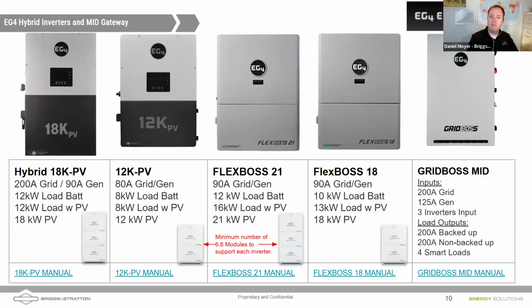So you can see with the 12K PV or the FlexBoss 18, that can only do 10,000 or 8,000 watts from battery to load. So that's the minimum number of batteries you're going to want to pair with these inverters, so that if the inverter is ever called upon to output its maximum output from batteries to loads, you're not going to be overloading the battery. The idea, though, here is that's the minimum, and there's going to be a lot of situations and applications where we're going to want more energy storage capacity than just a 2 battery stack that you see there.